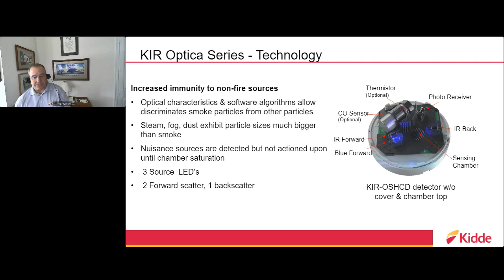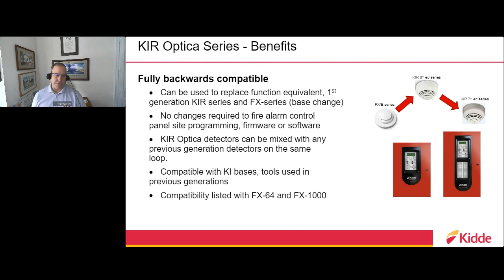So there's truly cost savings with this device. We've also made it backwards compatible with our legacy FX Kidde products out there today. Depending on the detectors connected to the Kidde FX panel, it could be as simple as replacing the detector into an existing base, or it could require changing out the base. But the key takeaway is it's a much higher level of technology that can be installed into a system today, and devices can mix and match on the same circuit—you don't have to replace all the detectors on that circuit. So if you had our 6th generation KIR detector, you could simply replace it with the 7th edition KIR detector, one for one, without replacing all of them. Again: technology and backwards compatibility are built into the product to support that.